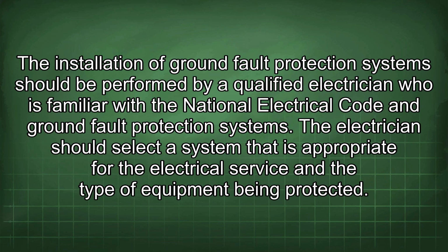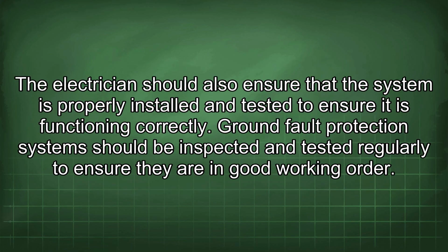The installation of ground fault protection systems should be performed by a qualified electrician who is familiar with the National Electrical Code and ground fault protection systems. The electrician should select a system that is appropriate for the electrical service and the type of equipment being protected. The electrician should also ensure that the system is properly installed and tested to ensure it is functioning correctly.